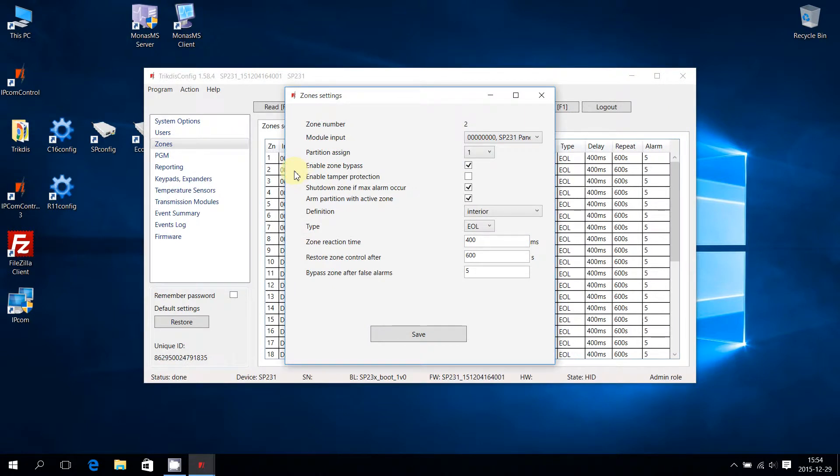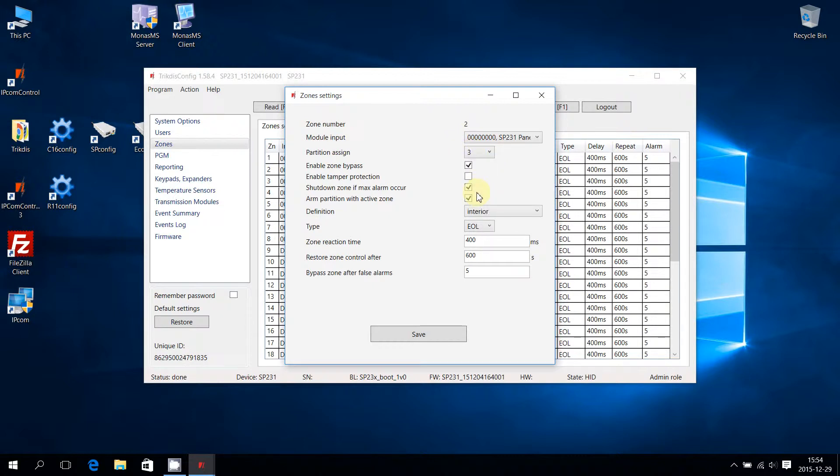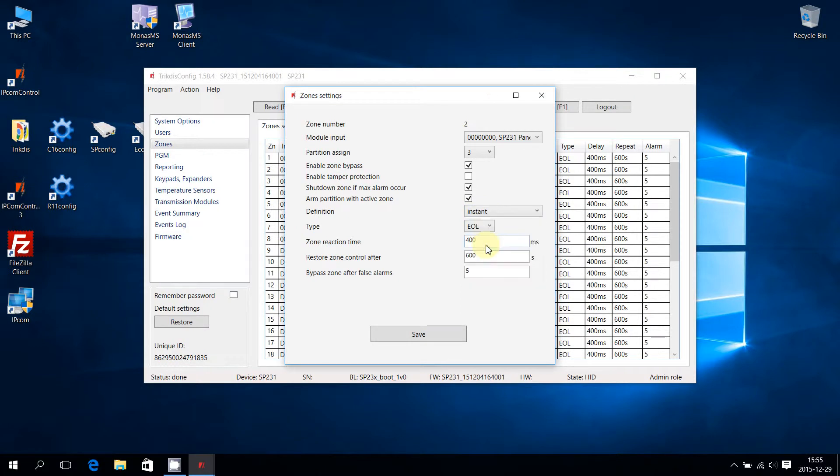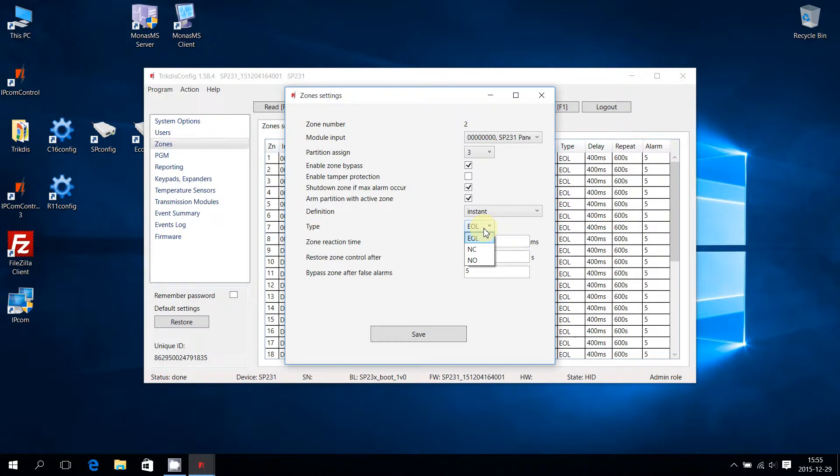Each zone must be assigned to a partition. It is selected from a partition assigned drop-down list. Zone's reactions are based on their selected definition. Choose appropriate definition for your zones from the definition drop-down list. Description of each type can be found in Control Panel SP231 Installation and Programming Manual. To trigger zone's reactions correctly, a right physical connection type must be selected. Available connection types are End of Line, Normally Closed, and Normally Open.